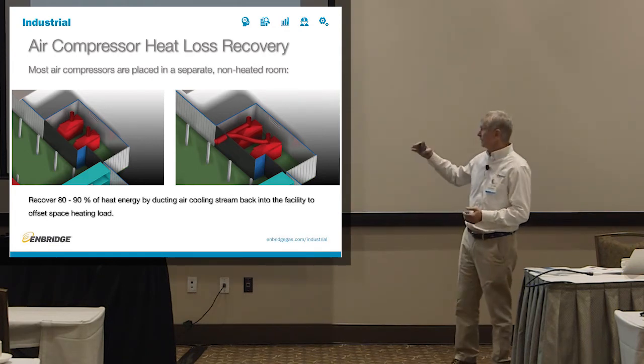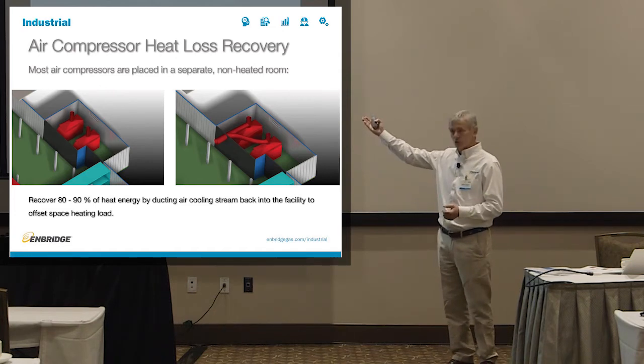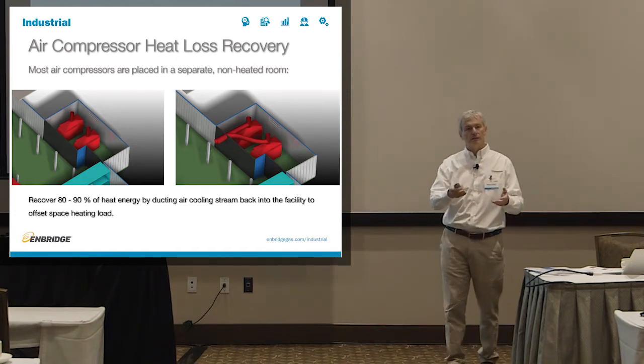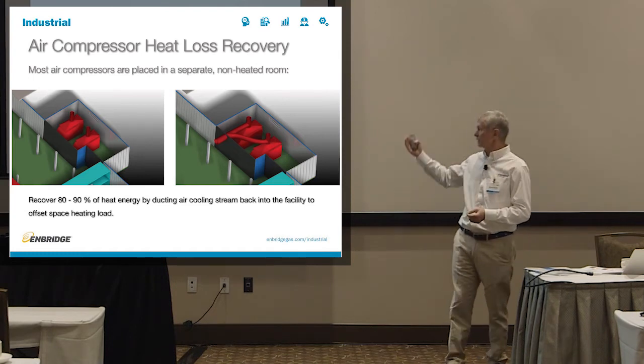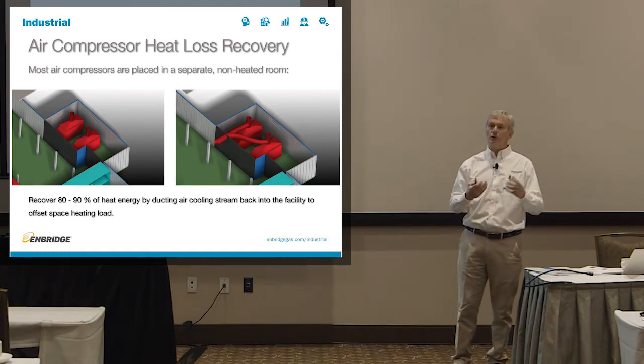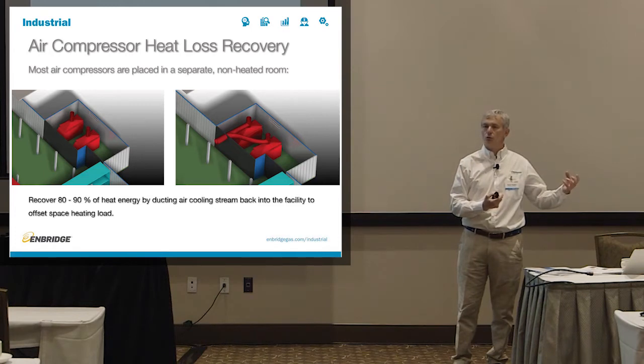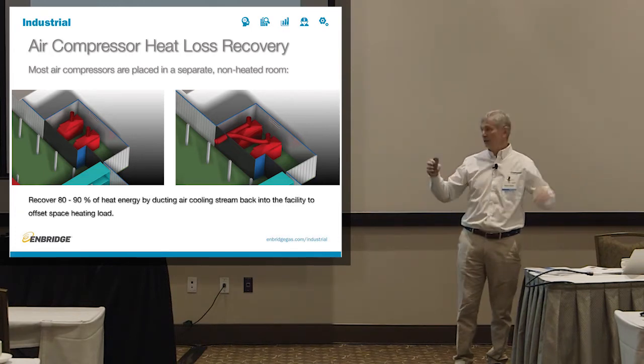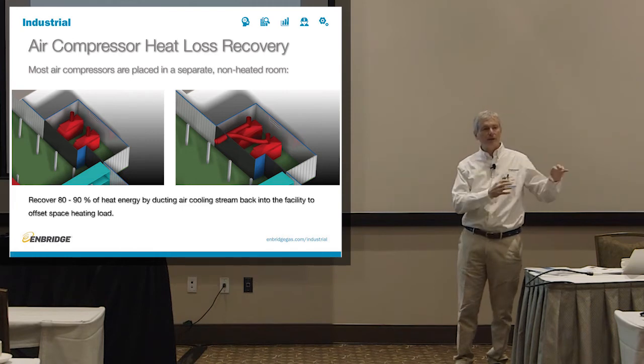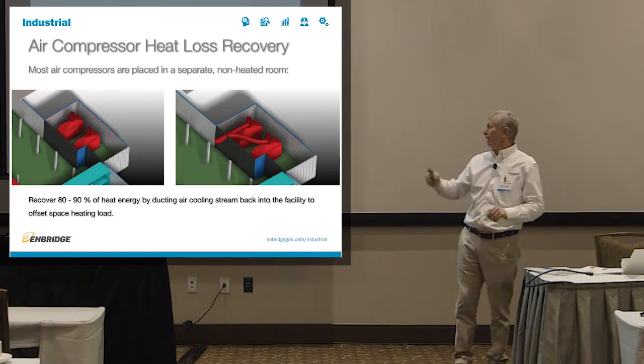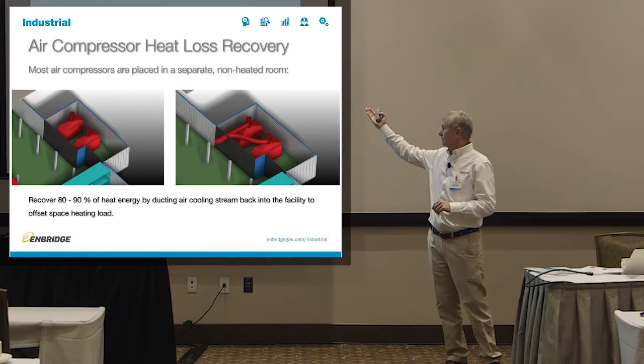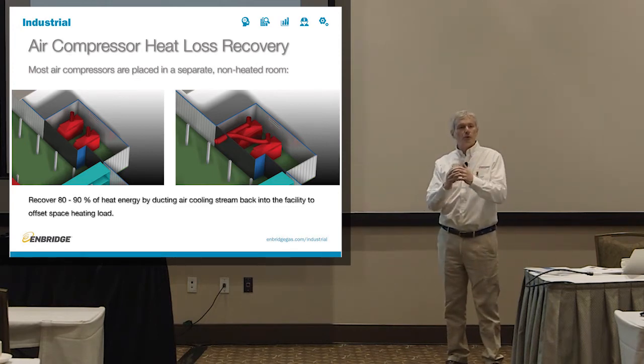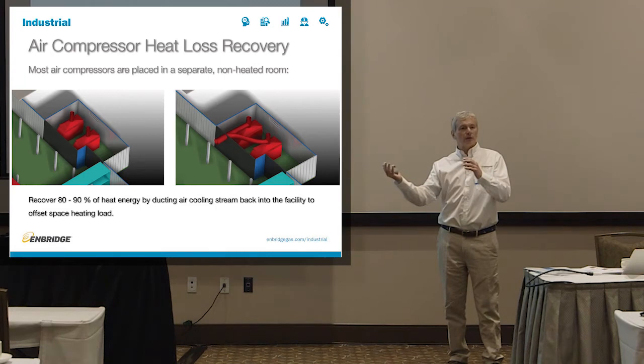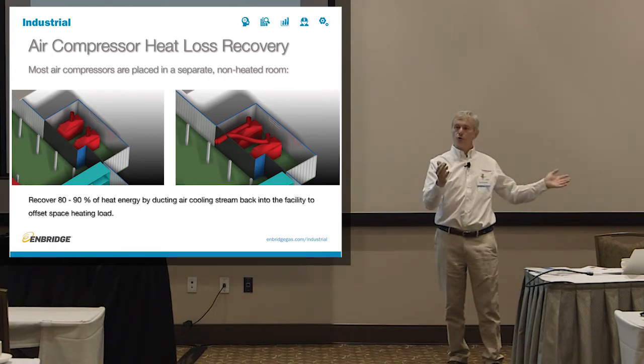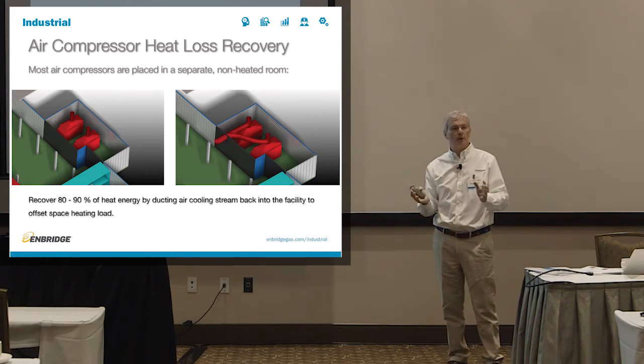And I've seen these applications can be very simple, just like shown there: hole in the wall, duct, that's it. Or it can be a little bit more complex, with a longer ducting system to take it where you need it, say in the shipping door area where it's always cold, and you dump all that air there. Then you need to put a fan in the duct to pull that heat further. I've seen people who have temperature controlled dampers in these exhaust streams. Depending on the outdoor temperature, the damper automatically closes or opens, allowing the hot air to go into the facility or outside. They don't have to worry about it.